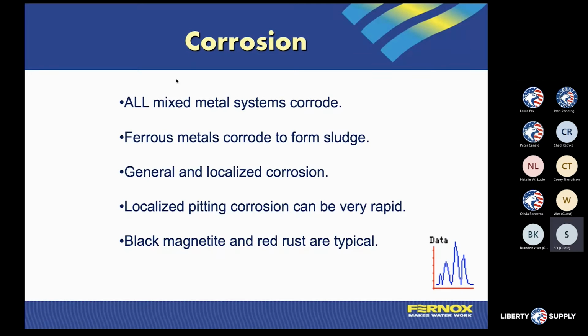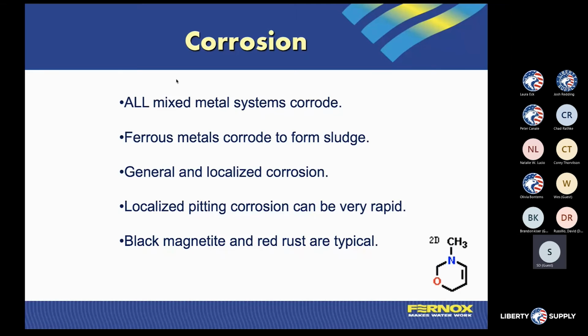When we go to assemble the system, you're going to have a mix of steel and copper and PEX and stainless and different metallics. Then we're going to get into some of the chemical components. If you're using press fittings, you have silicone as the lubricant that they use on that system. When we get into any kind of solder joint, you're going to have flux, and Teflon tape, and pipe dope, and all of these different components. And then we're going to have that connected all together. We're going to run our fluid through that, and inevitably we're going to pick up some of those products.